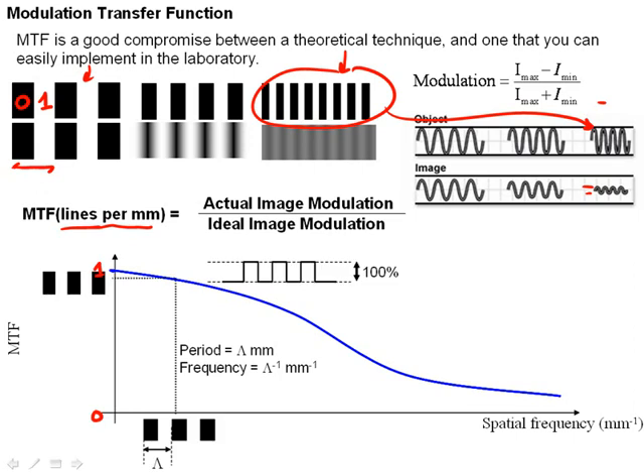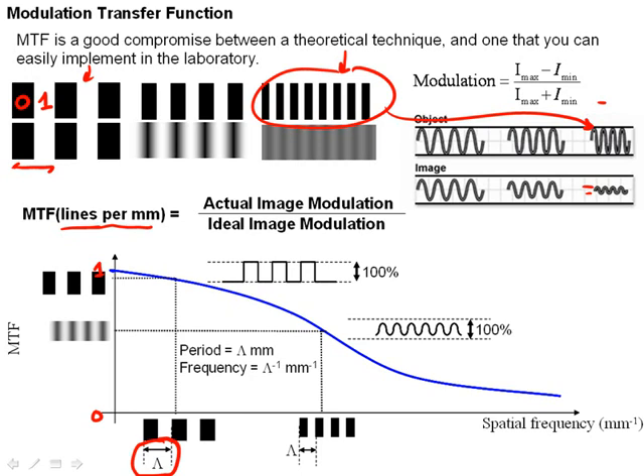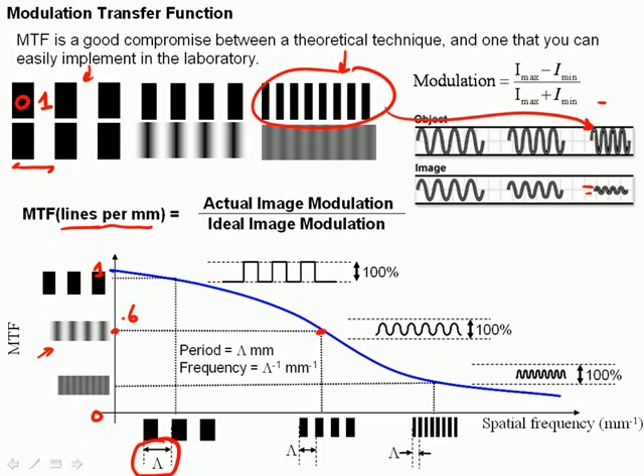So let's take a look at an example here. For bars with a large period, here, with good spacing, the image might look like this. The white areas are almost completely white, the black areas are almost completely black, and our modulation transfer function here has a value near 1 because there's about 100% difference between the bottom and the top. However, as we get our bars close together, our spatial frequency becomes higher as the period gets smaller. You'll notice that we don't have an image that looks like perfectly black and white bars here anymore. The modulation is less than 100%, and you'll notice here our value may be on the order of 0.6, as we calculated above, and as the bars get still closer together, the image looks less and less, or has a little less and less contrast. The bars start to blur into a uniform gray. The modulation is much less than 100%, and so we're getting down to values around 0.2 here, and the imaging system gets worse and worse until we go to high enough frequencies, the modulation transfer function drops to zero.